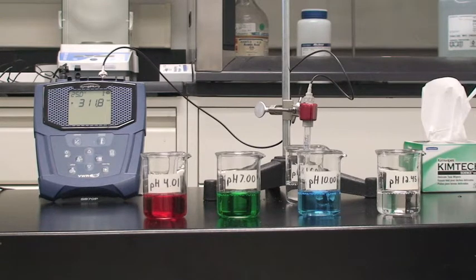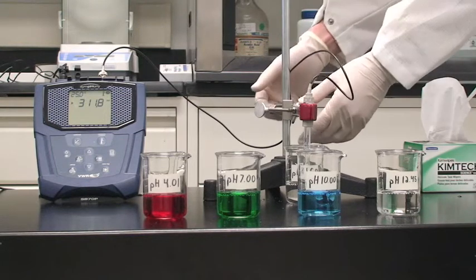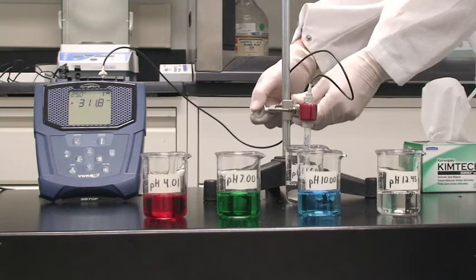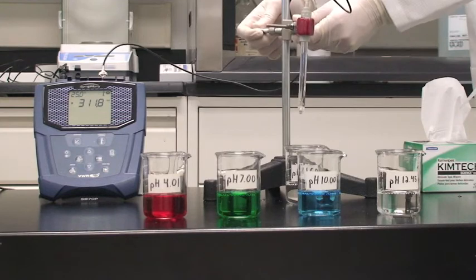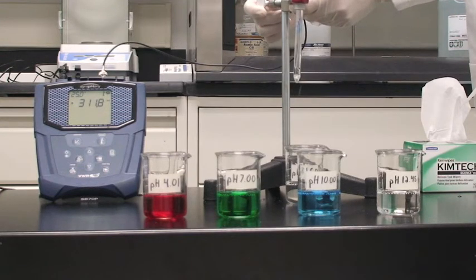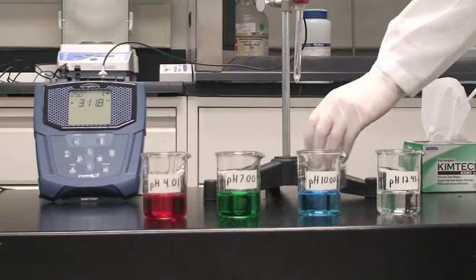The icon on the right edge of the screen will flash until a stable reading is obtained. Once the flashing stops, we have our potential. We can now remove the probe from solution, rinse, dry, and repeat in the other test solutions.